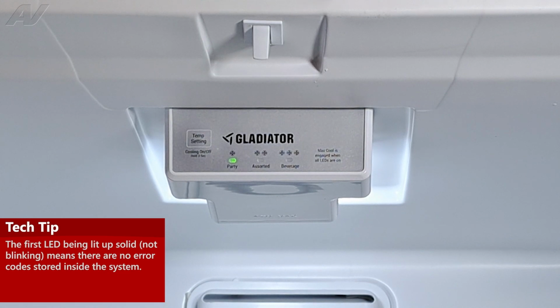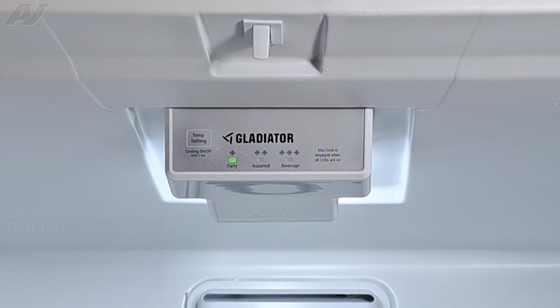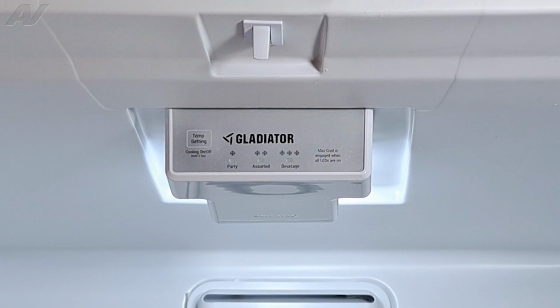At the very end, the LEDs will turn off, and then you might have a couple of different error codes that could pop up inside the system. Each one of these error codes are distinguished by different LED lighting that can appear. I'm going to give you an example. The first error code that might pop up would be if LED 1 is blinking. This is going to be a control problem. Then you may have where LED 2 is blinking, which is the middle LED. This is going to be for a temperature sensor error code.